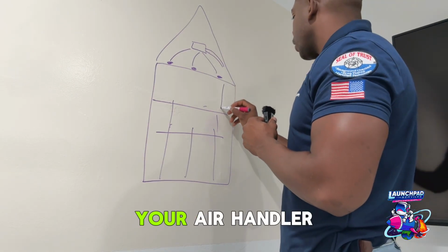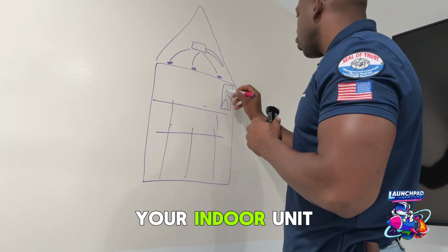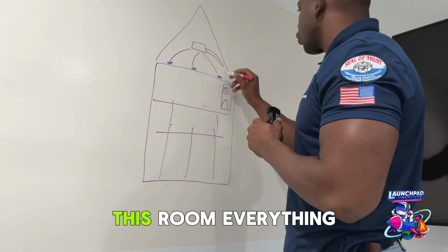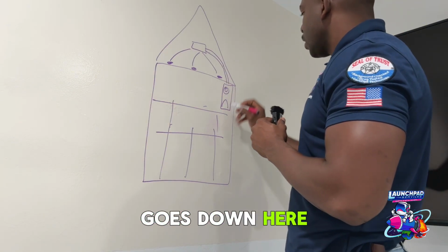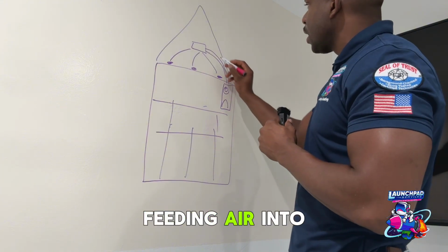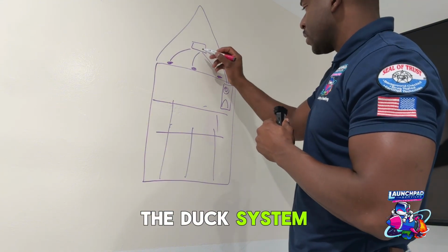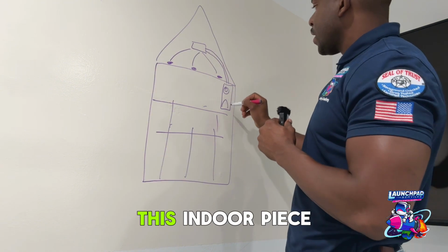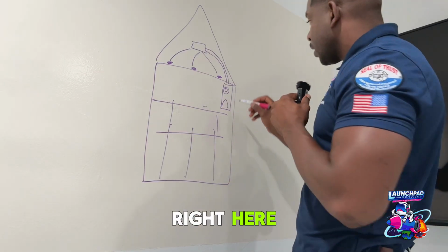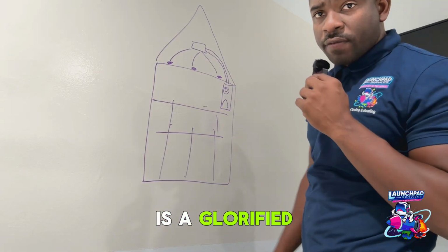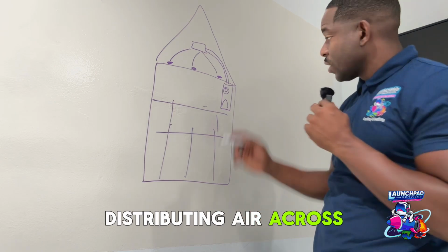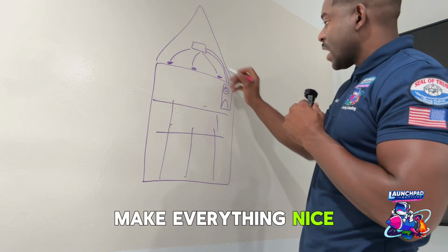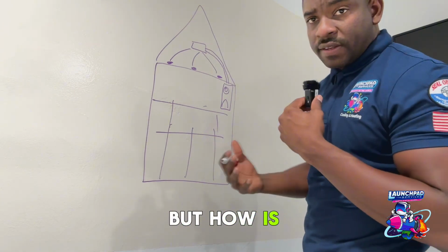Say, for example, your air handler unit, which is your indoor unit, is located in this room. Everything goes down here. The system is feeding air into the duct system, and pretty much this indoor piece right here, all it is, is a glorified fan distributing air across this coil to make everything nice and cold. But how is it made cold?